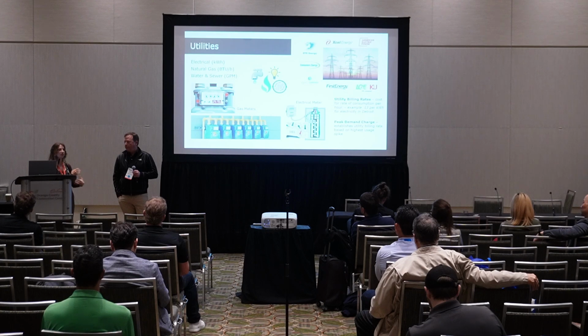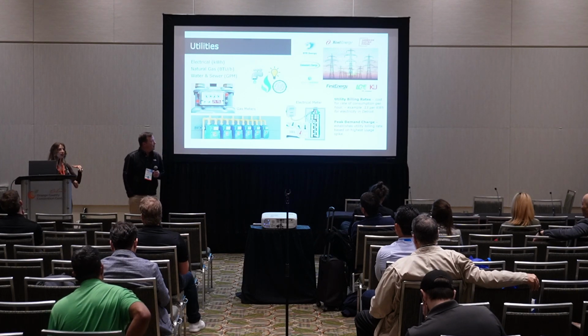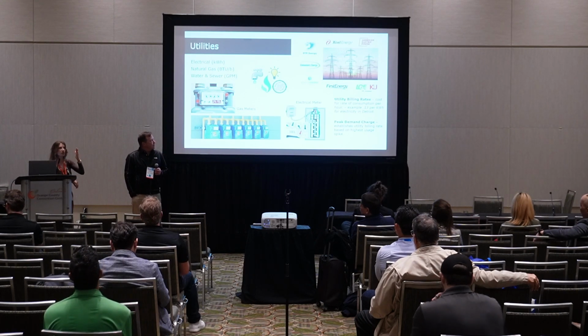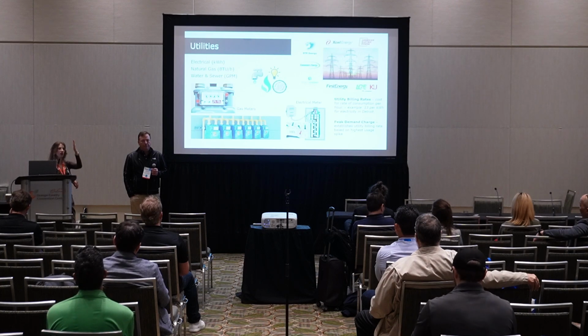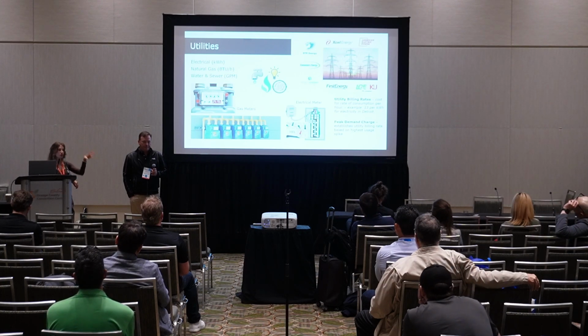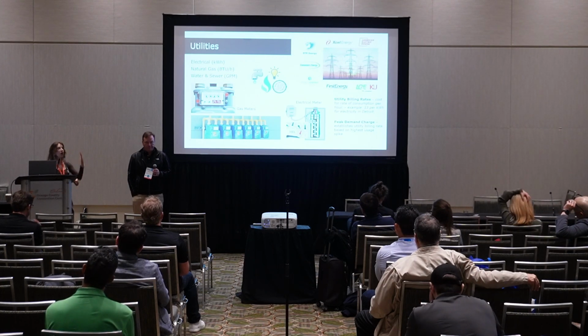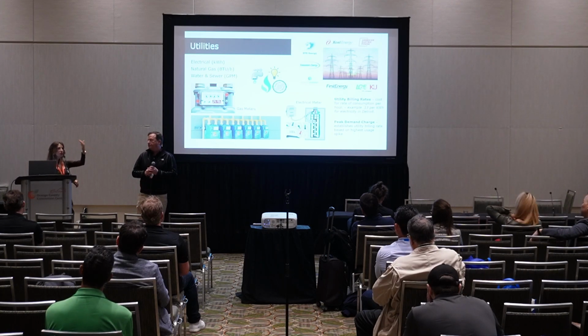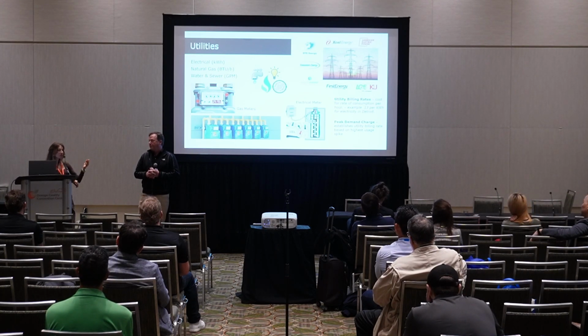So you have to do things slowly, which is why typically you want a load management strategy to get ahead of it, with controls in place so you know, like, my boiler is coming on at peak demand, so I'll change the strategy rather than waiting until I've reached my limit and turning everything off, only for it to all turn back on again with the same peak, just half an hour later, and now everyone's mad.